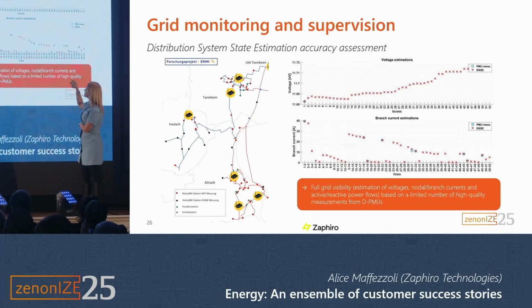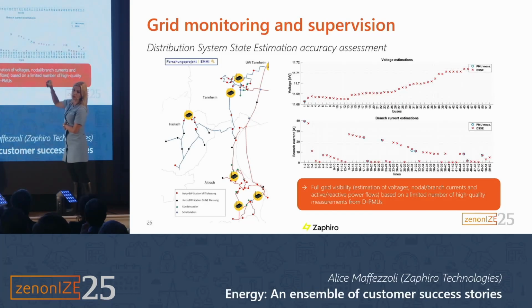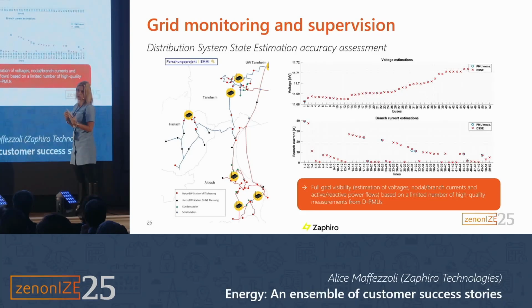So this is what happens. I don't know if you can see, but I will explain it better. The first graph shows the voltage, and the second one is the current. The blue circles are the measurements, while the red crosses are the estimates. In the first one, we just have 1 measurement in the primary substation because we measure voltage only in the primary substation. For the currents, we have more measurements because in the secondary substations, we also measure current. I forgot to mention that we measure current through Rogowski coils, so it is a non-invasive installation. That's why in the secondary substation, it's really non-invasive, because we don't need to measure voltages. As you can see, you get a very precise state estimation because the estimates correspond to the measurements.